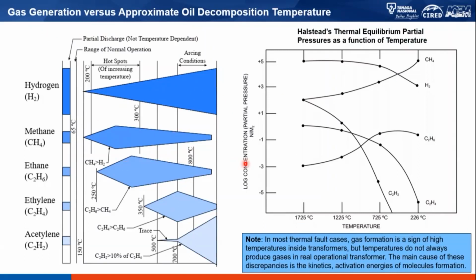This slide is trying to show that hydrogen, for example, can be initiated at a temperature as low as 150 degrees, and it will increase as the temperature increases. Methane is around the same, and will also increase. Ethane is a bit higher in terms of initiation, and ethylene at 350 degrees would be initiated. Acetylene, which we call the arcing gas, will be initiated if there is a fault causing a very high temperature of more than 700 degrees C.